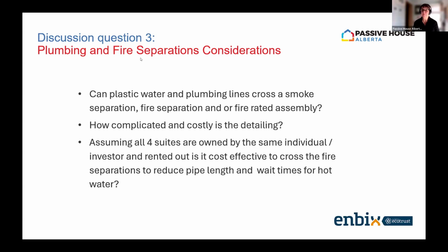Stuart: You'd have to do a Part 6 design, and you'd have to use an HRV with less than 3% leakage to be allowed to do a central unit. And that adds a ton of cost, you need fire dampers, you need engineering for everything. You 100% wouldn't be able to do that.